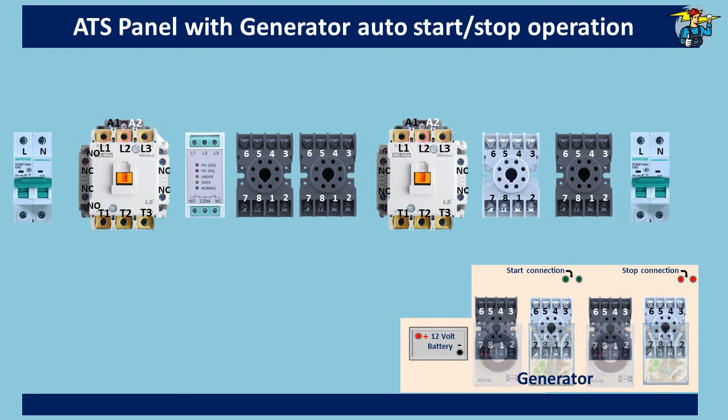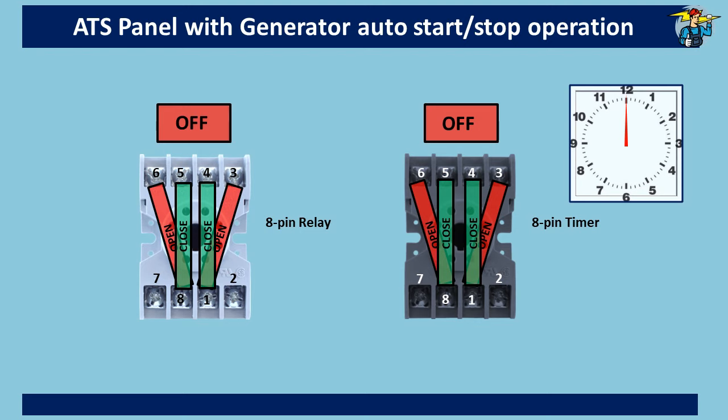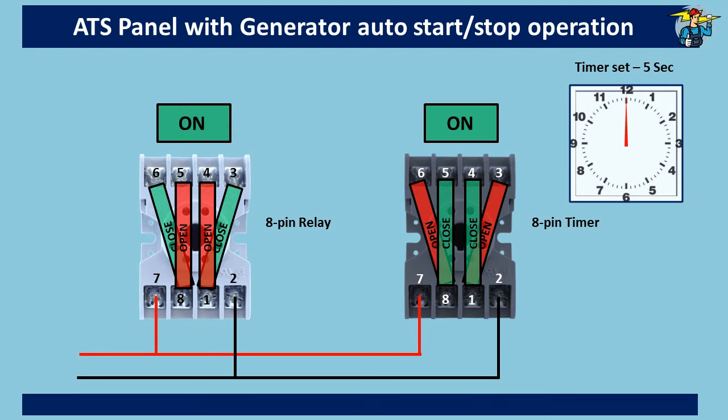Generator auto-start connection points and stop connection points are also shown here. If you take out the timers and relays from their bases, you will see the numbers on those ports. These are called DPDT — double pole double throw timers and relays. Double pole means there are two separate input ports numbered one and eight. Double throw means each port has two outputs: one normally closed and the other normally open. Ports seven and two are the power connection ports. As soon as these get power, normally closed points open and normally open ports close. The relay switches instantly, but the timer waits till a set time — for example five seconds — before interchanging its ports.